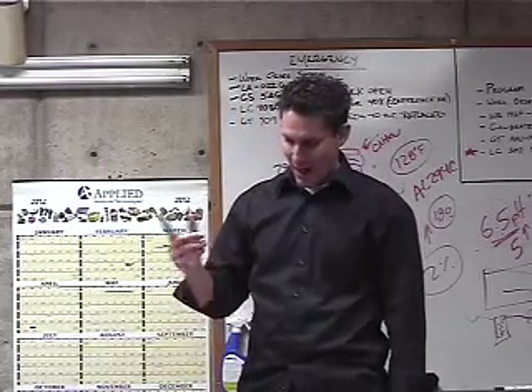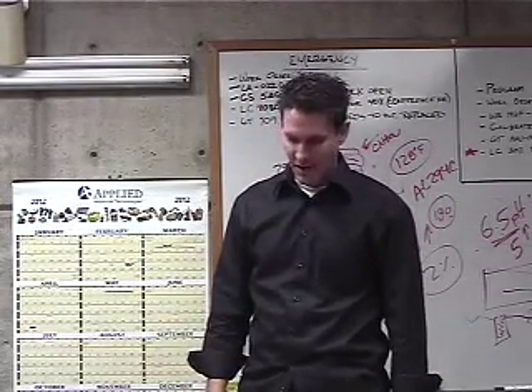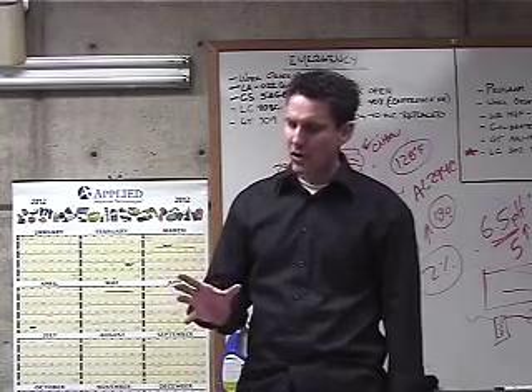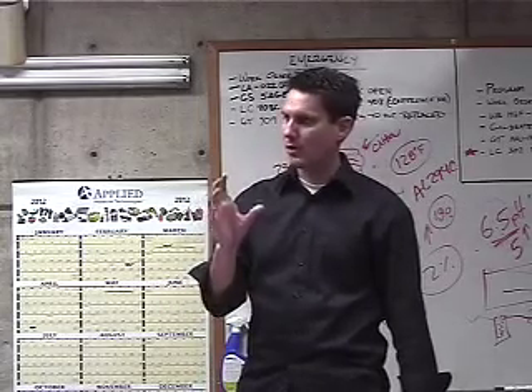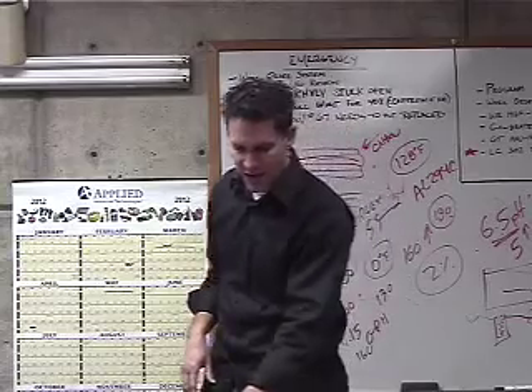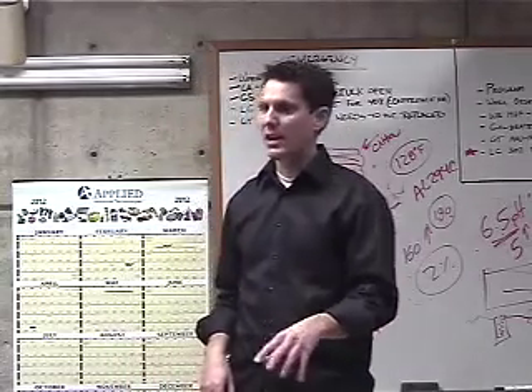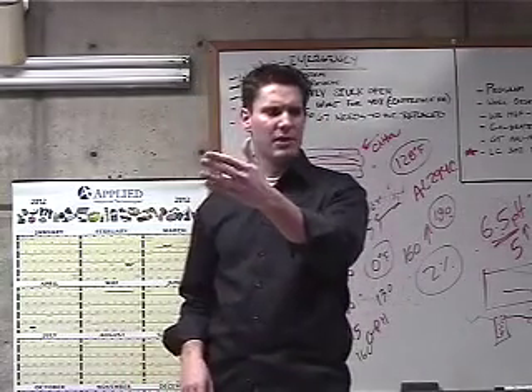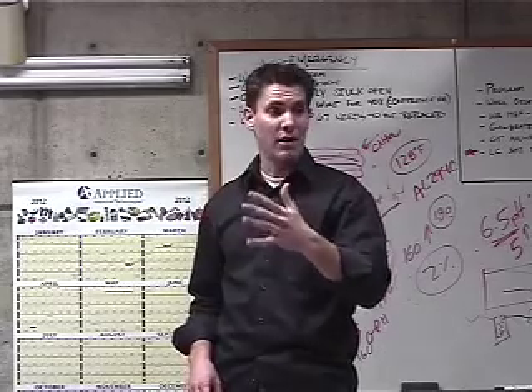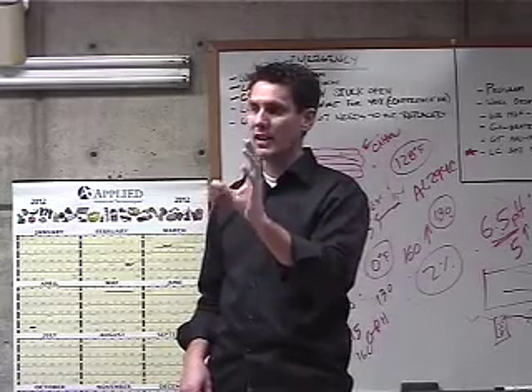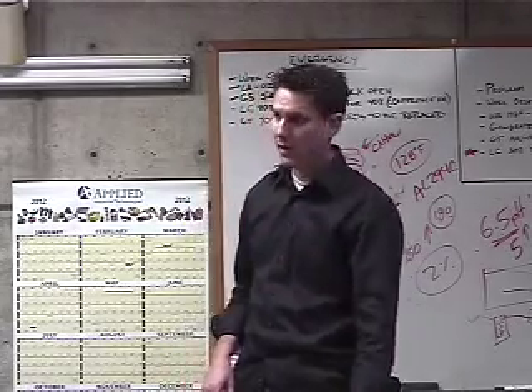Okay. What were we talking about? Carbon. The carbon and the soot. So you've got to make sure to check that and check the flame, the quality of your flame. When we get into the daily maintenance, that is something that you should be looking at every day. Now I don't think your boilers are going to be operating every day, but when they are operating, make sure that you look down there and you just check that flame quality every day. It'll tell you what the flame should look like.